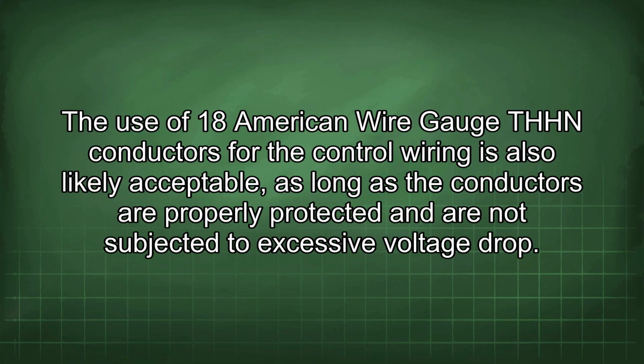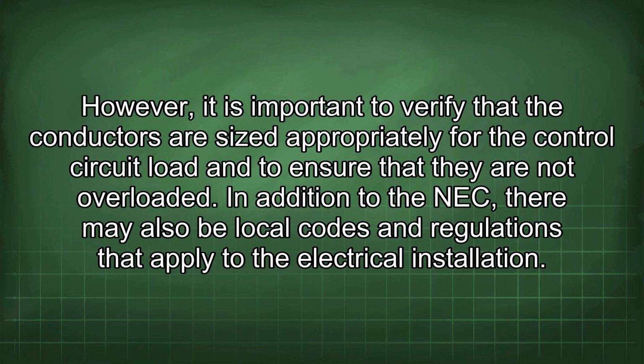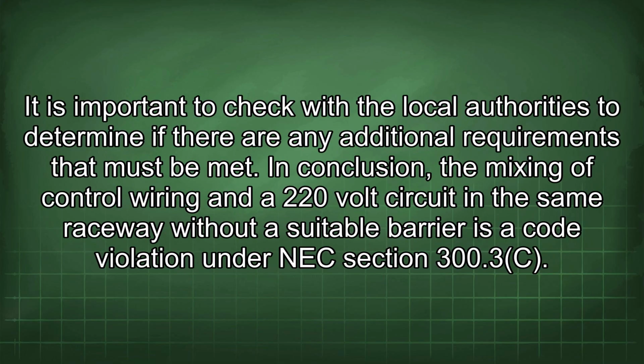The use of 18 American wire gauge THHN conductors for the control wiring is also likely acceptable, as long as the conductors are properly protected and are not subjected to excessive voltage drop. However, it is important to verify that the conductors are sized appropriately for the control circuit load and to ensure that they are not overloaded. In addition to the NEC, there may also be local codes and regulations that apply to the electrical installation. It is important to check with the local authorities to determine if there are any additional requirements that must be met.